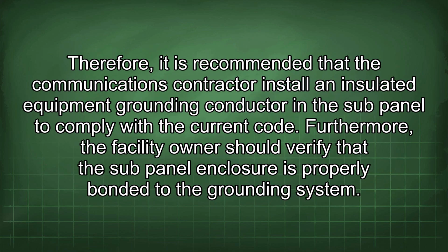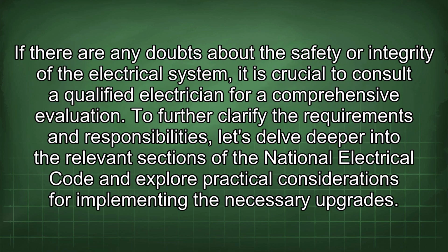Therefore, it is recommended that the communications contractor install an insulated equipment grounding conductor in the sub-panel to comply with the current code. Furthermore, the facility owner should verify that the sub-panel enclosure is properly bonded to the grounding system. If there are any doubts about the safety or integrity of the electrical system, it is crucial to consult a qualified electrician for a comprehensive evaluation. To further clarify the requirements and responsibilities, let's delve deeper into the relevant sections of the National Electrical Code and explore practical considerations for implementing the necessary upgrades.